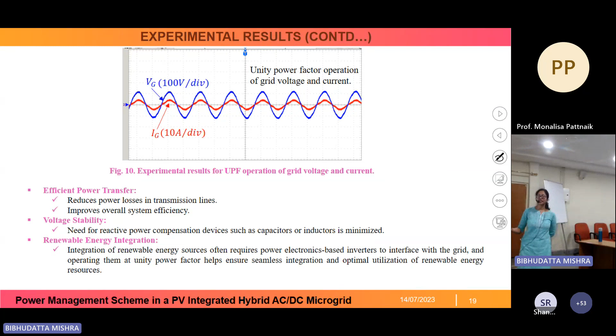Now, another main requirement of a hybrid AC/DC microgrid is to operate the system at unity power factor. Here we can see the grid voltage and grid current are operated at unity power factor. Because of operation at UPF, we can reduce transmission losses. Also, we can improve voltage stability so that extra compensation techniques are not required in the system. And also for renewable energy integration, it is required so that we can seamlessly integrate renewable energy sources to our grid.